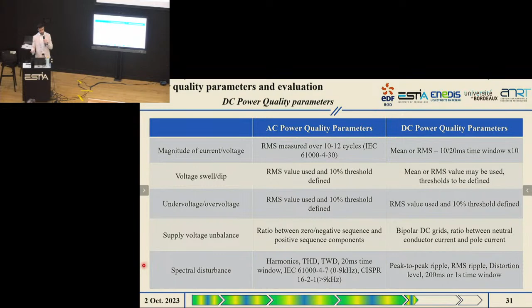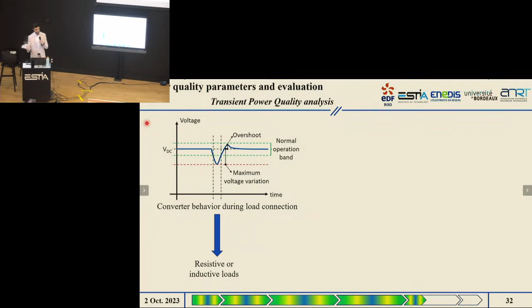total distortion level. And once we defined the main parameters that could be used to evaluate power quality in a DC system, we focused our efforts in terms of transient analysis on two main indicators, which are voltage swells and voltage dips, that in DC are mainly caused by the connection or disconnection of loads. And we found out during our work that to prevent damage in equipment and to guard a certain level of compatibility with sources and loads, we could act in the control of the power converter in order to mitigate the influence of voltage swells and voltage dips, coming either from the AC side or from the DC side.